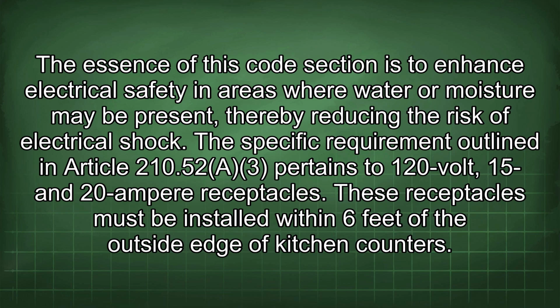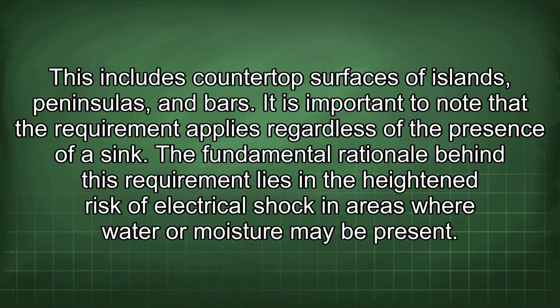The specific requirement outlined in Article 210.52(A)(3) pertains to 120-volt, 15 and 20 ampere receptacles. These receptacles must be installed within 6 feet of the outside edge of kitchen counters. This includes countertop surfaces of islands, peninsulas, and bars. It is important to note that the requirement applies regardless of the presence of a sink.